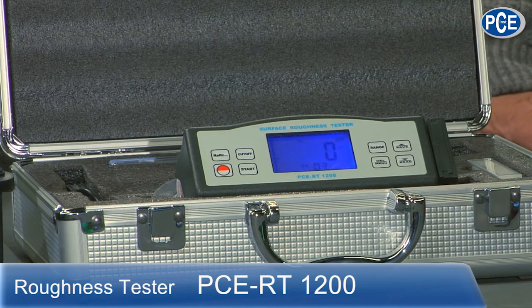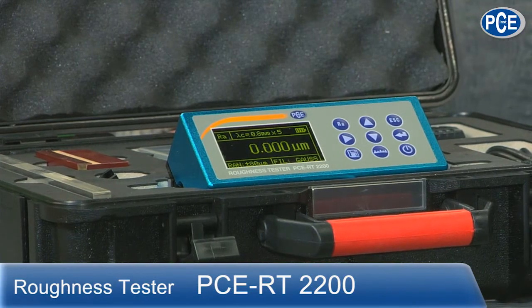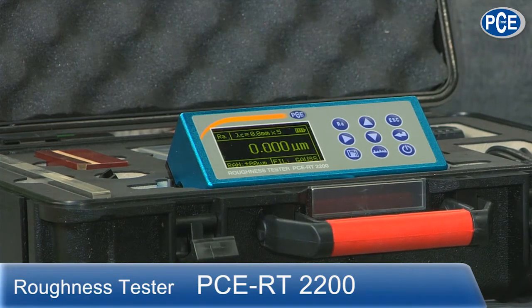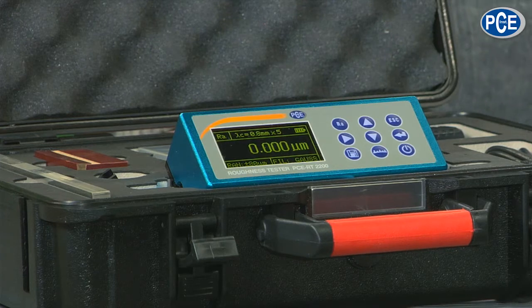Lots of possibilities for the settings, and it is very flexible, with which it is possible to measure many different surfaces, and the height can be adjusted with a foot. Also with the last device, the PCE-RT2200, that would also be adjusted using the foot. You also have a level with which you can read if the head is properly adjusted, and the device can handle up to 14 parameters in one measuring step - save, record, and show graphically.